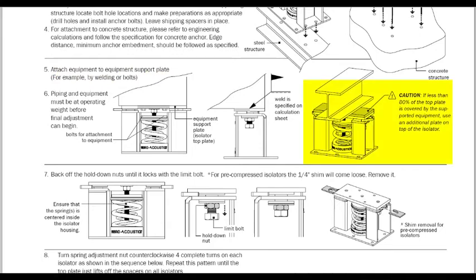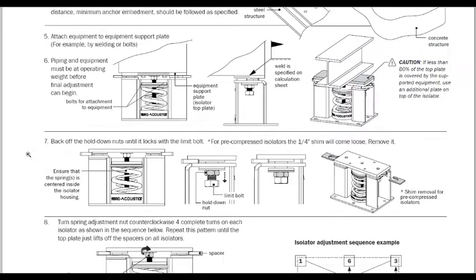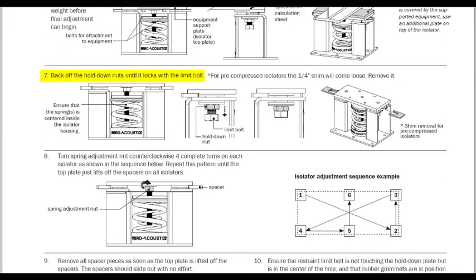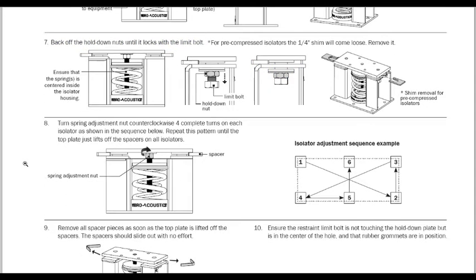This image here better explains the 80% rule, where an extra top plate is required to add additional stiffness and prevent sagging during installation. Though not explicitly stated here, it would be expected that the equipment or steel beam would be welded to the extra top plate, and it in turn would be welded to the isolator top plate. The next step shows that the contractor needs to move the hold-down nut to touch the head of the limit bolt. This will allow the equipment to float. This step is often missed, so we'll want to check that this has been done.